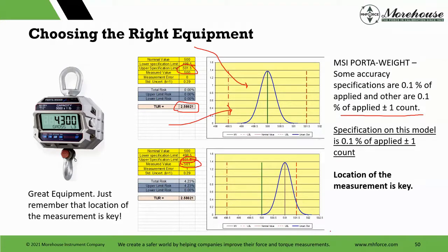Here it reads counts by 1 pound, right? So we're either going to read 500 or 501. At 501, our risk is 4.23%. So really great equipment. Surprisingly, the specifications are really tight on these, but about 80% of them that come into our lab are in tolerance. The purpose of this slide was just that location of the measurement is key, but as I messed up on it, also understanding what they're saying. Is the specification plus or minus 1 count, or is it just one count?